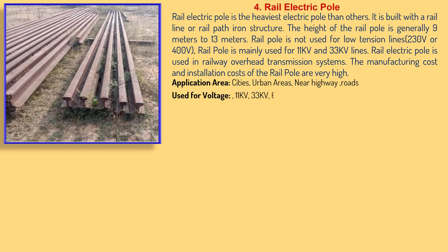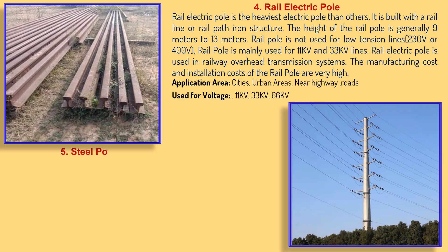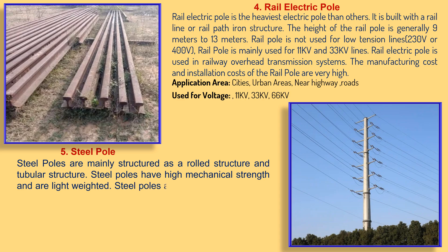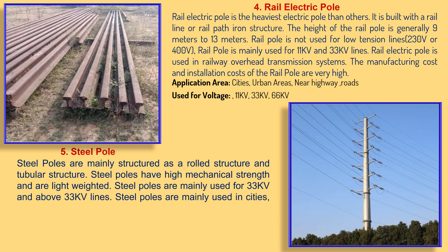Steel poles are mainly structured as a rolled structure and tubular structure. They have high mechanical strength and are lightweight. Steel poles are mainly used for 33kV and above lines, and are used in cities, urban areas, near highways and roads. The installation and manufacturing cost of steel poles is high. They are capable of withstanding more loads, wind, and sag than wooden, PCC, and RCC poles.